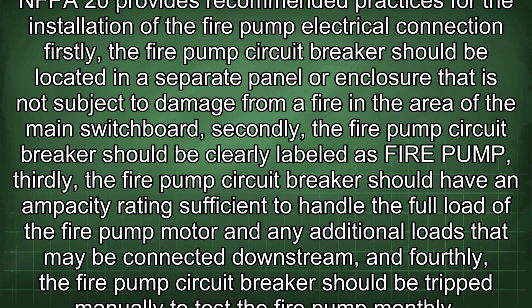Firstly, the fire pump circuit breaker should be located in a separate panel or enclosure that is not subject to damage from a fire in the area of the main switchboard. Secondly, the fire pump circuit breaker should be clearly labeled as fire pump.